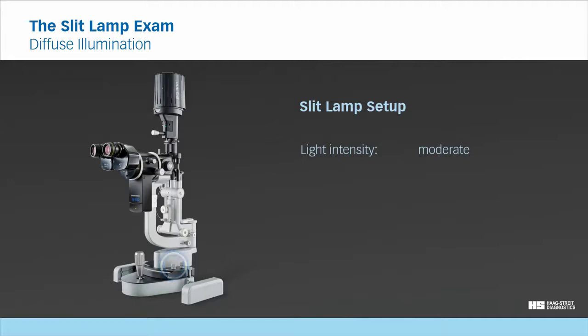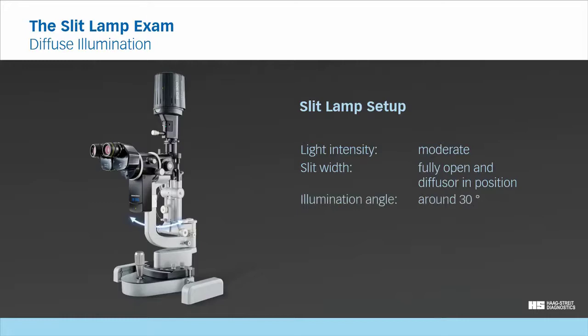Slit lamp setup. To set up the slit lamp, choose a moderate light intensity. Bring the diffuser in position and open the slit completely. Alternatively, you can switch on a dedicated background illumination. Select an illumination angle somewhere around 30 degrees for ensuring even illumination. We recommend a magnification of 6 times or 10 times.